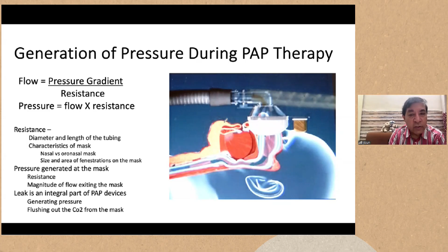So this is very important for you to understand, because in the panel discussion later on, you will be talking about leaks, different types of leaks. So leak is an integral part of this system, and the leak which is required to produce a pressure is called essential leak or the intentional leak, which has to be there. So it not only generates pressure but also flushes out the carbon dioxide of the expired air.